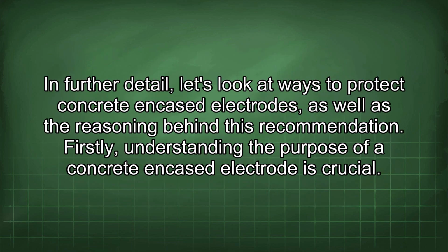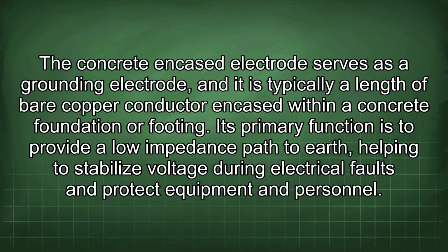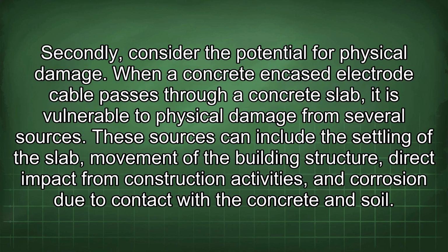In further detail, let's look at ways to protect concrete encased electrodes as well as the reasoning behind this recommendation. Firstly, understanding the purpose of a concrete encased electrode is crucial. The concrete encased electrode serves as a grounding electrode, and it is typically a length of bare copper conductor encased within a concrete foundation or footing. Its primary function is to provide a low impedance path to earth, helping to stabilize voltage during electrical faults and protect equipment and personnel.